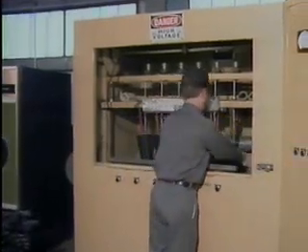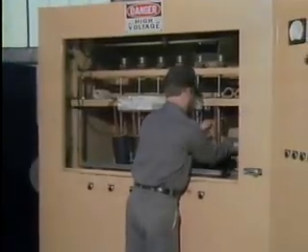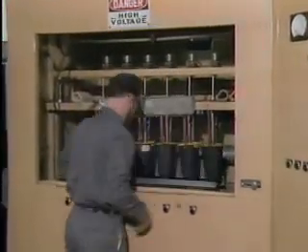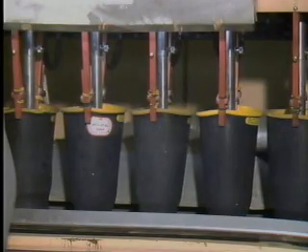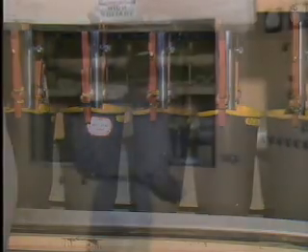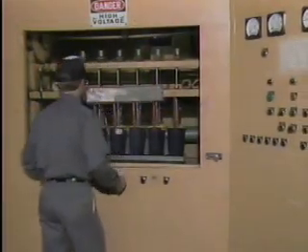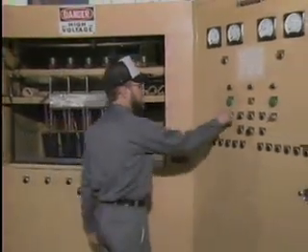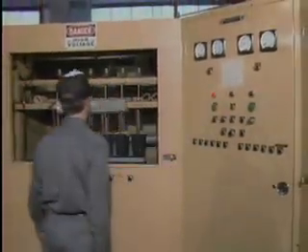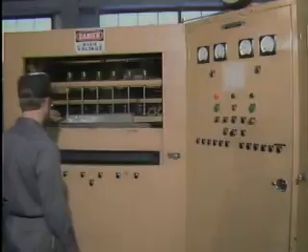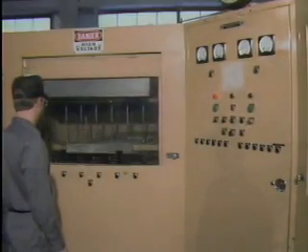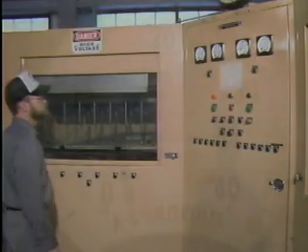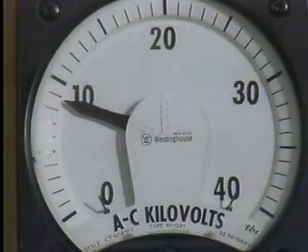This is a test apparatus that's used to perform dielectric tests on insulating gear. The apparatus can test 6 gloves at a time. Each glove that's being tested is first filled with water and then lowered into a water-filled tank in the apparatus, which is connected to ground. A hot lead then applies the test voltage to the water inside the gloves. The technician monitors the test by watching a current meter to be sure the leakage current through the gloves remains within acceptable limits.